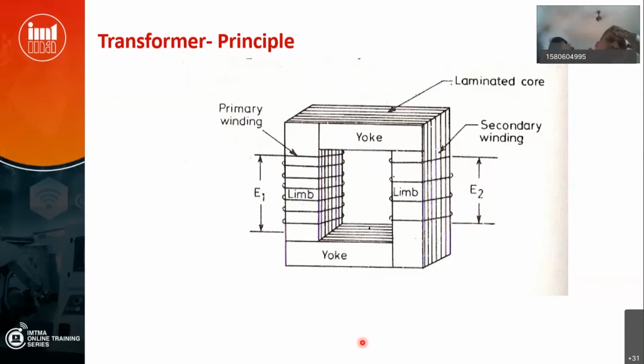So large distance transmission takes place at the higher voltage, and the current is very small. Then it is taken into a receiving station. There you can step down 400 to maybe 220, maybe 110, maybe 66, depending on your requirement. Then finally, when you come to your roadside distribution transformers, where it feeds domestic loads, that is 11 kV to 415.